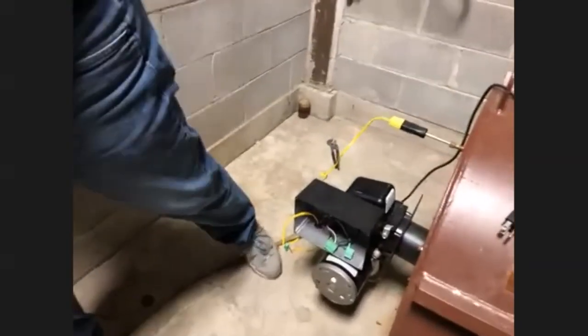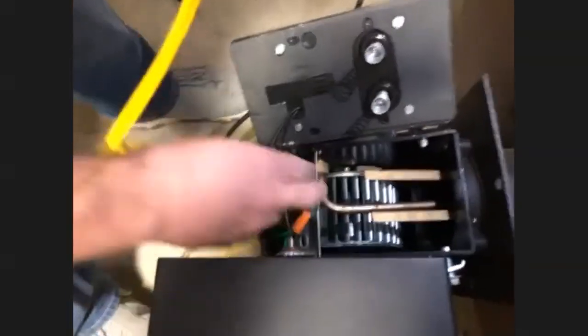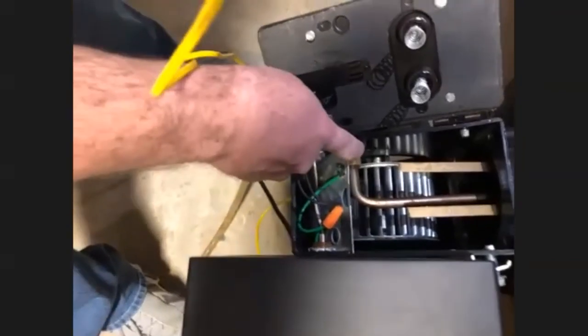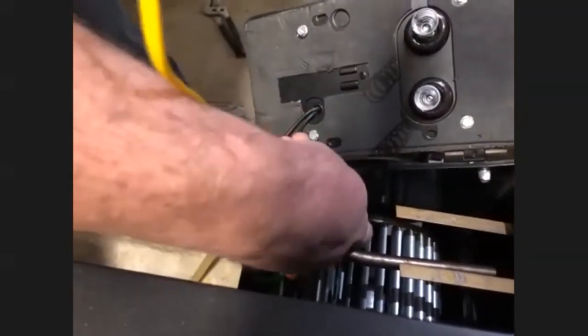The gun assembly. I'll keep this control board off. And the gun assembly on the oil burner: you want to open up the transformer door. For the gun assembly, there's a fitting right here. You loosen that fitting, take it off. That sets the gun assembly itself. That's your fuel line. So once you remove that, you can take that out and you would completely remove the entire gun assembly.